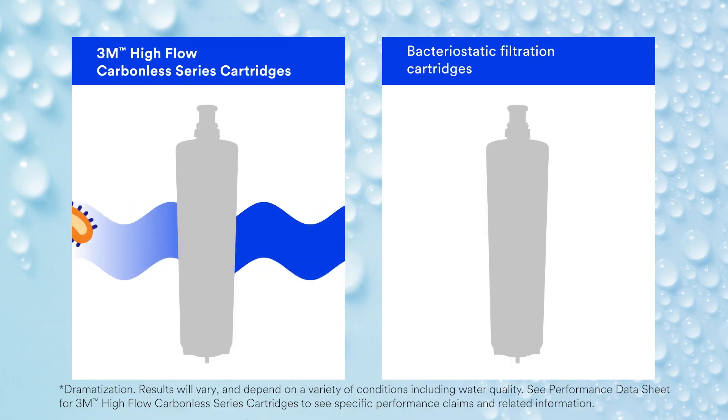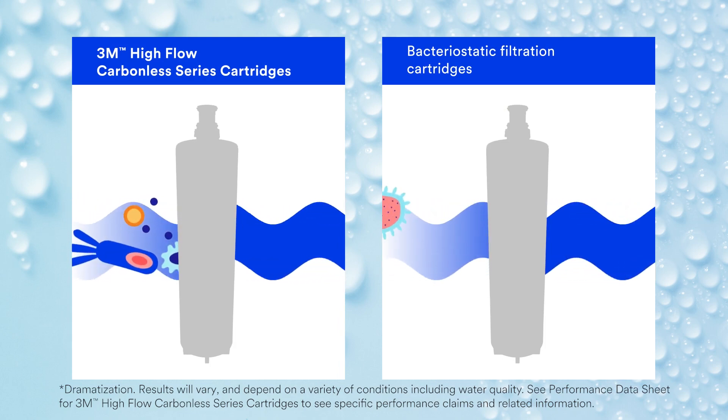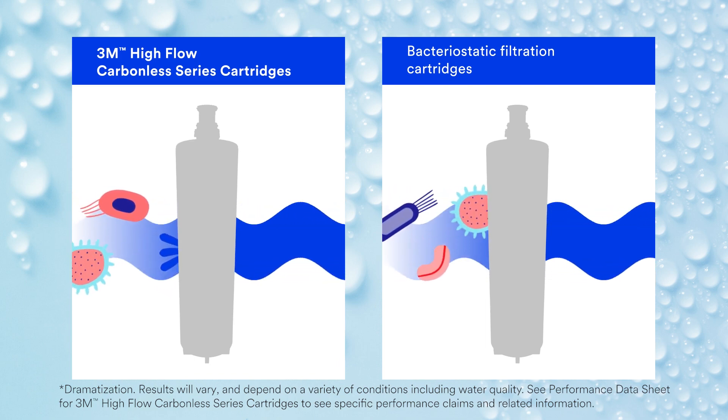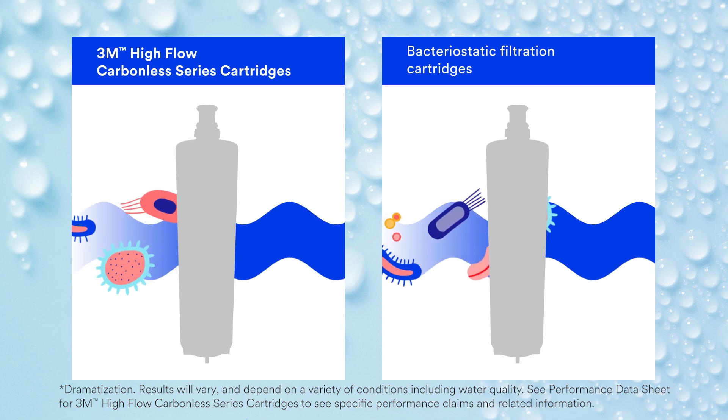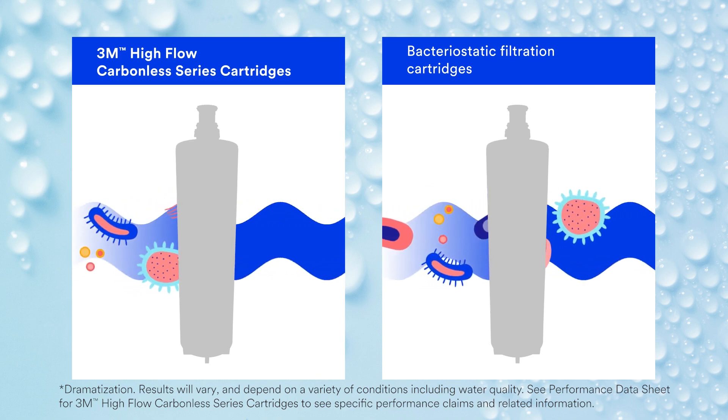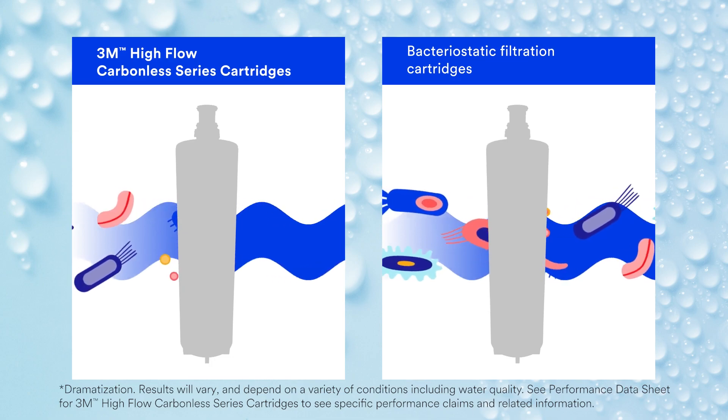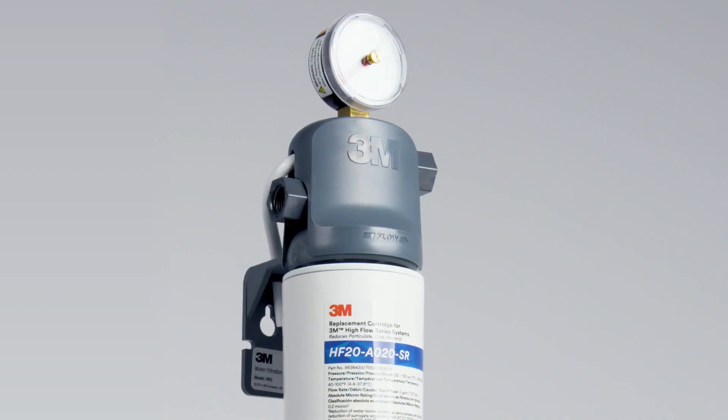3M's high flow carbonless water filtration cartridges retain and reduce the bacteria levels in water, which is dramatically different than bacteriostatic filtration cartridges. Bacteriostatic cartridges simply limit the ability of bacteria to grow within the filter, but the bacteria may not be reduced and can still be present in the water.